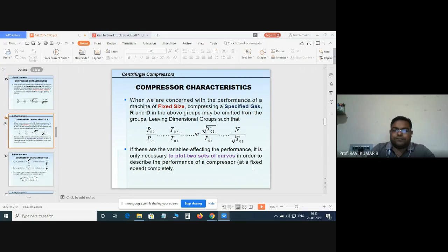P02 by P01 is the static head non-dimensional parameter, and T02 by T01 is the temperature head parameter. There is a mass flow rate parameter and there is the speed parameter. If these are the variables affecting the performance, it is only necessary to plot two sets of curves in order to describe the overall performance of a fixed speed compressor. These are the two curves which can be drawn: P02 by P01 versus non-dimensional mass flow rate, that is m dot root T01 divided by P01, for a fixed value of speed, or temperature ratio T02 by T01 versus non-dimensional mass flow rate for a fixed speed.